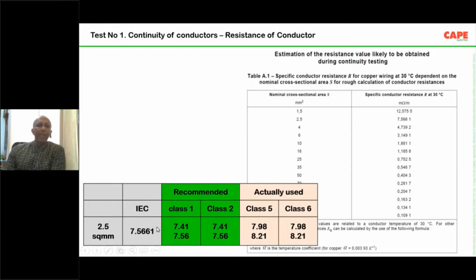If we look at the reference value given in IEC, 7.56, that means we are supposed to use a conductor of class 2. It's a flexible conductor. Then, not only in India, worldwide, there are two more kinds of conductors available, class 5 and class 6. Class 5 is called a highly flexible wire. This wire is generally used for panels, because inside a panel board you have to twist it and make wiring through very sharp edges and turns. And here another point is that inside a panel board, the length of the wire is very short. You are not using it over a longer distance, let us say 50 meters. Inside a panel board, it may be 2, 3, 5 or 6 meters, not larger sizes.